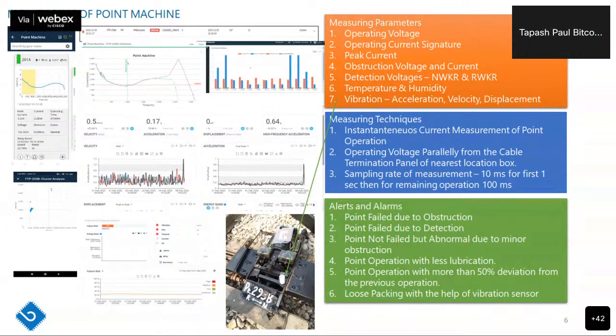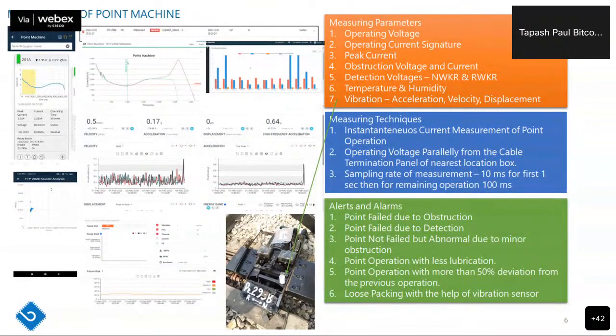We are generating alarms. These are the typical alerts and alarms that we are getting right now, and we are deriving them from this data. Point failed due to obstruction: whenever a hard obstruction is there, we get the alarm because the operation time is increased. Point failed due to detection. Point not failed but abnormal due to minor obstruction: it is not failed, but after 2-3 operations it can fail. Point operation with less lubrication. Point operation more than 50% deviation from its previous operation. Loose packing with the help of vibration sensors. These are the alerts and alarms we are deriving.